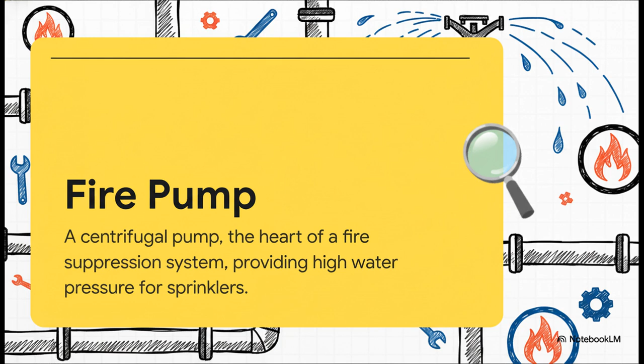The scale we are talking about here is just mind-boggling. The installation manual requires a concrete foundation that weighs at least 2.5 times more than the entire pump setup itself. So why so huge? Because when this machine kicks into gear, it needs a base that can absorb every single vibration, every jolt, and every shock without moving an inch. It has to be immovable.